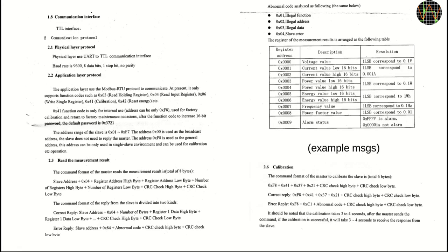And speaking of those, to read or set the registers, the module uses a serial interface using TTL levels with pretty standard parameters as you can see. The protocol uses the Modbus interface standard and the instructions assume you are at least half familiar with it. If you have used it before or read some of the online documents on Modbus, it's pretty simple.